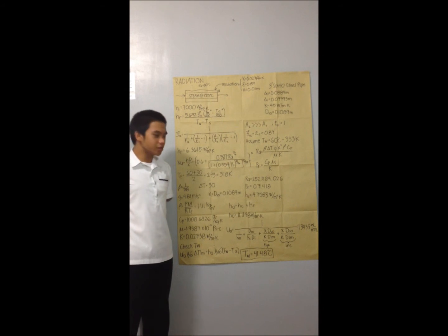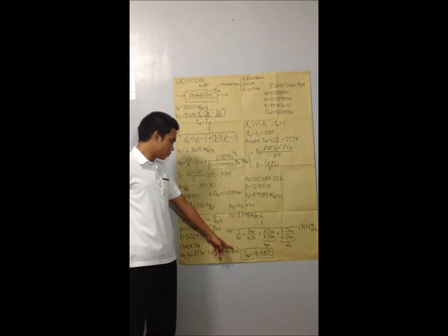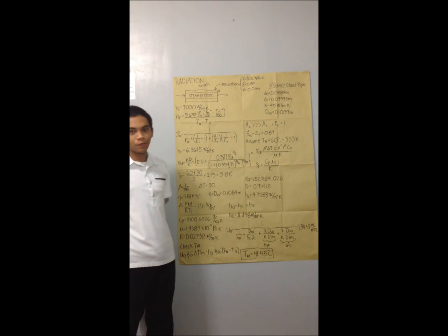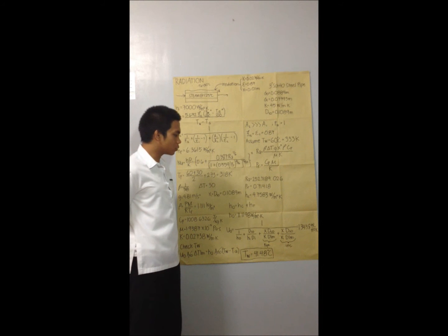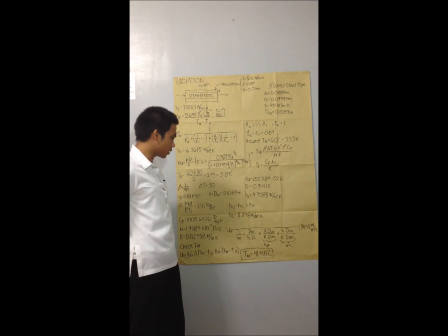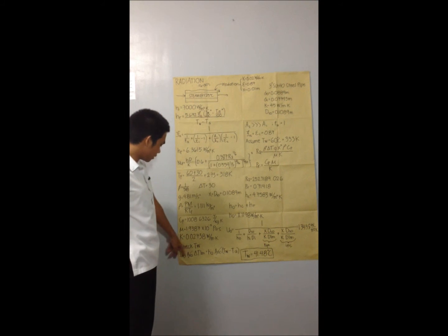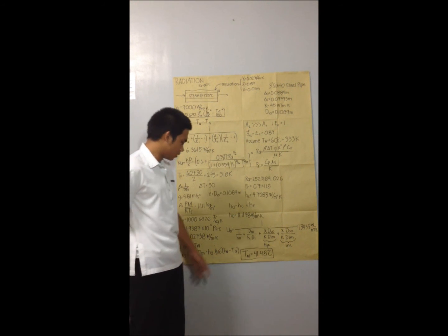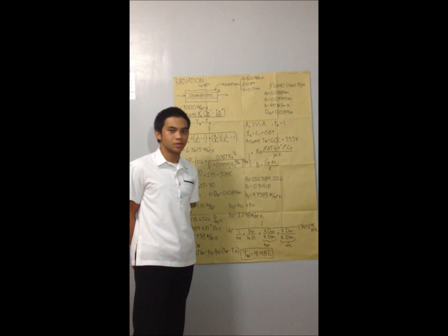And since this is radiation, we always use U_O. We need U_O in order to check our wall temperature at steady state. We can solve for U_O given this equation, and it will give us 1.3438 watt per meter squared Kelvin. And we can substitute this value in the steady state equation here, cancelling the area, and it would give a wall temperature of 41.48 degrees Celsius.